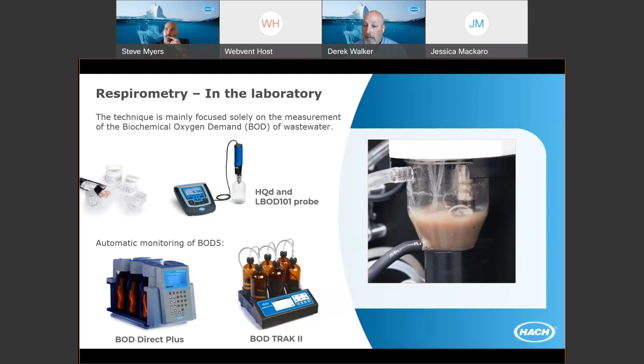And on the next slide, Steve, we will see several different types of laboratory tests or specific technologies that can be run. Of course, a BOD probe can be used with an automatic stirrer to stir the sludge. The BOD5 test, this uptake rate test, is done over 5 days to correlate with the BOD5 method or the CBOD5 method, and that is measuring oxygen consumption and then converted to milligrams per liter of BOD that is consumed. Alternatively, you can use an automated instrument for process control. The BOD Direct Plus is pictured here, or the BODTrak 2. And some of the unique features of these instruments is that you can do some experimentation and actually modify the time period that these oxygen uptake tests are run, so that it can give you some process control data using an automated laboratory instrument.